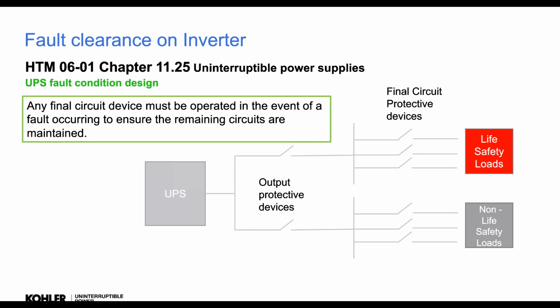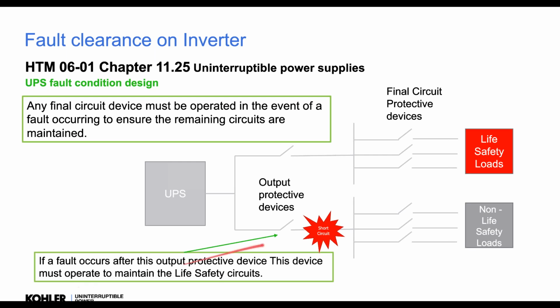You do, however, if you have a central UPS feeding multiple circuits. If we have a fault here now, we need this to operate because we need this load to run. I mean, ideally, we shouldn't be having non-life safety loads and life safety loads on the same thing, but people do it. And if we have a short here, we do want to trip that breaker. Sub-main breakers get more difficult to trip than final circuit MCBs. We have to fully understand the UPS and the circuit breaker to make sure we can operate that breaker.